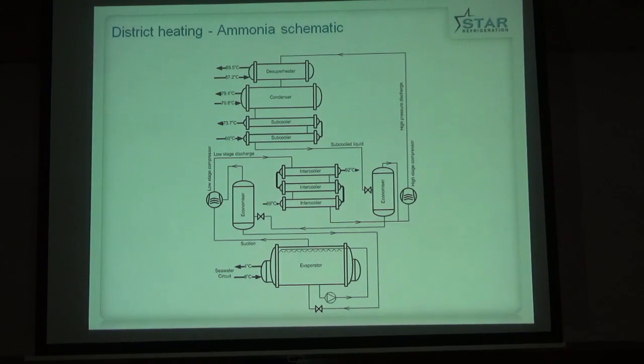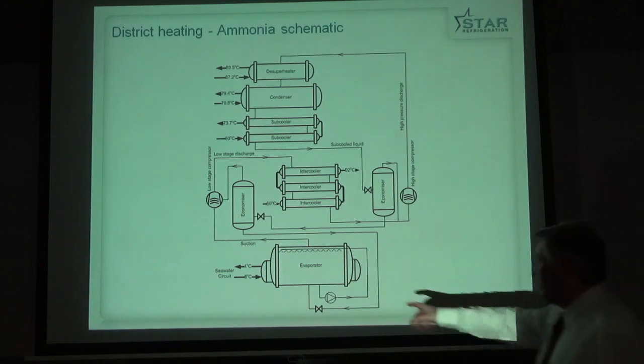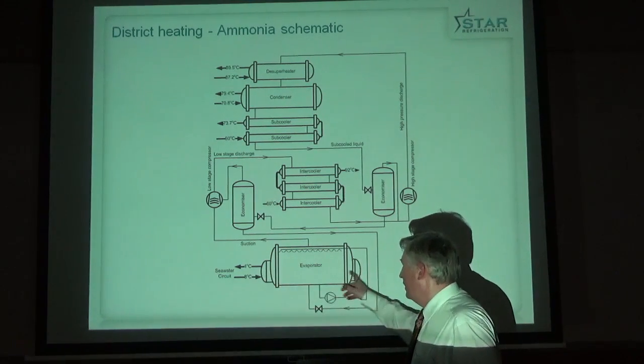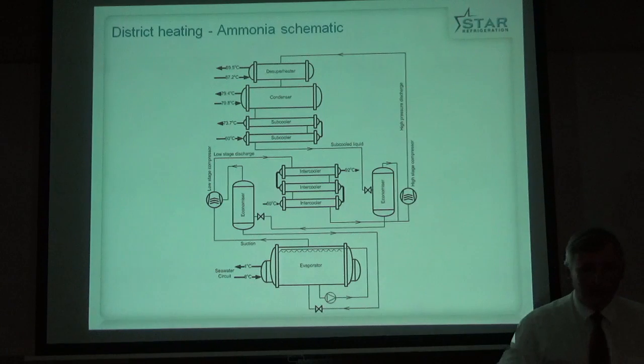This is a schematic of the ammonia circuit. The heat pump has got two compressors. It's got an intercooler between condenser, desuperheater, subcooler at the top. So we're heating up the water by running it through the condensing side of the system, and at the same time we're taking river water at 8 degrees, putting it through the evaporator and chilling it down to 4 degrees.